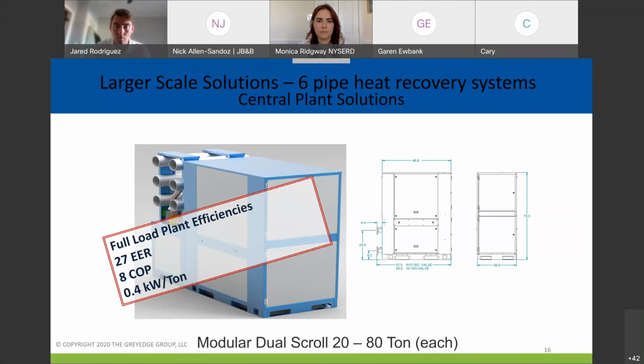If it's under 410A, it's probably got a top range of about 120 degrees Fahrenheit, maybe 130 if we want to push it. But we can also chill and make ice, do a hockey rink on the cold side. It's a matter of what we do. And the way these 6-pipe systems work is there's a supply and return for the chilled water side, a supply and return for the hot water side.